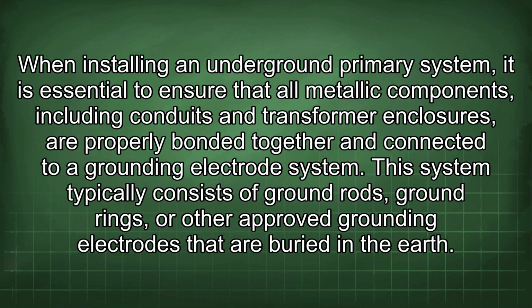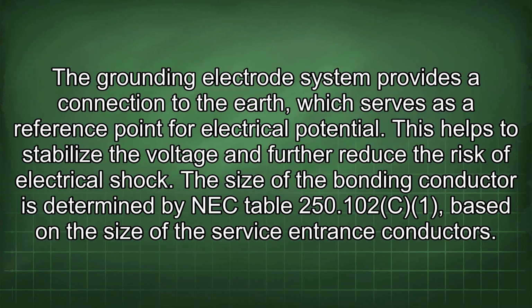When installing an underground primary system, it is essential to ensure that all metallic components, including conduits and transformer enclosures, are properly bonded together and connected to a grounding electrode system. This system typically consists of ground rods, ground rings, or other approved grounding electrodes that are buried in the earth. The grounding electrode system provides a connection to the earth, which serves as a reference point for electrical potential. This helps to stabilize the voltage and further reduce the risk of electrical shock.